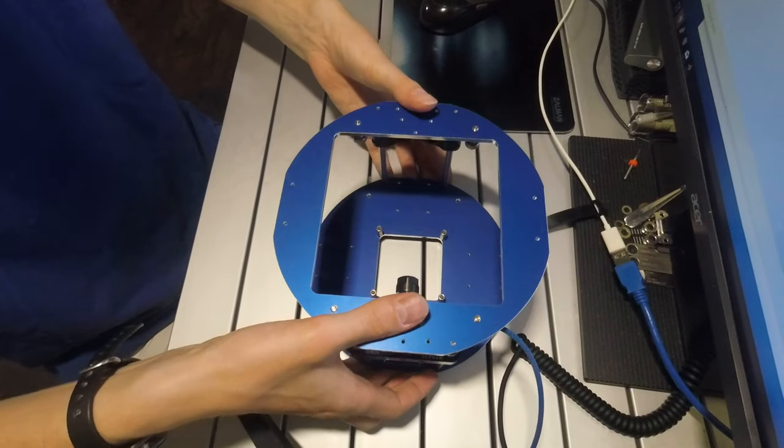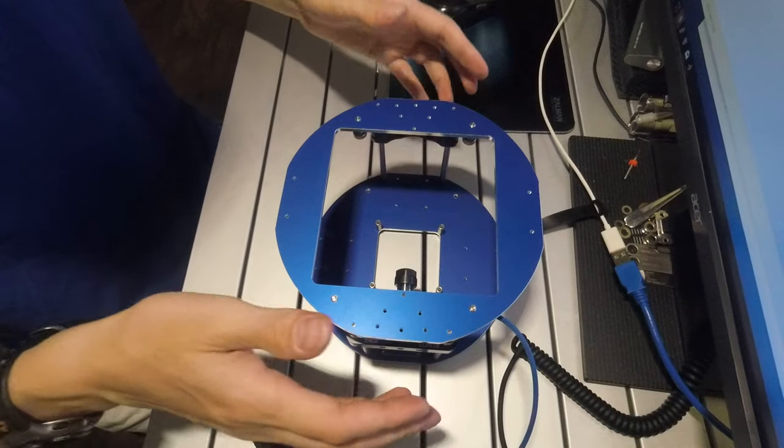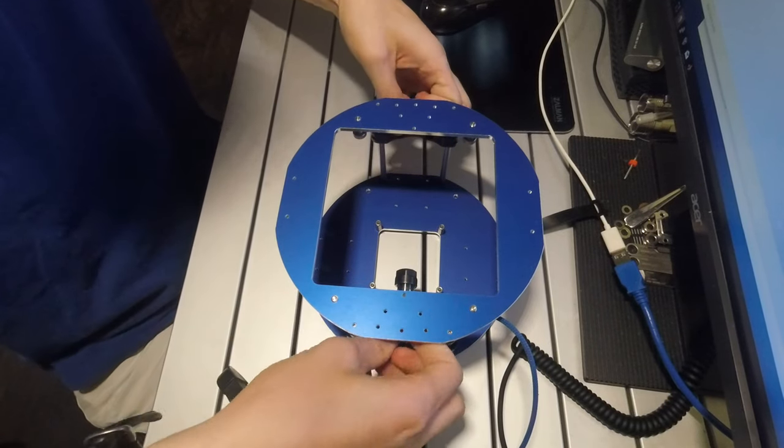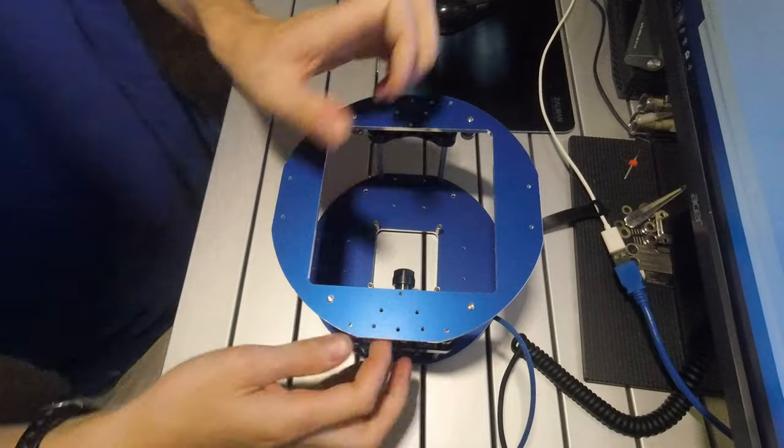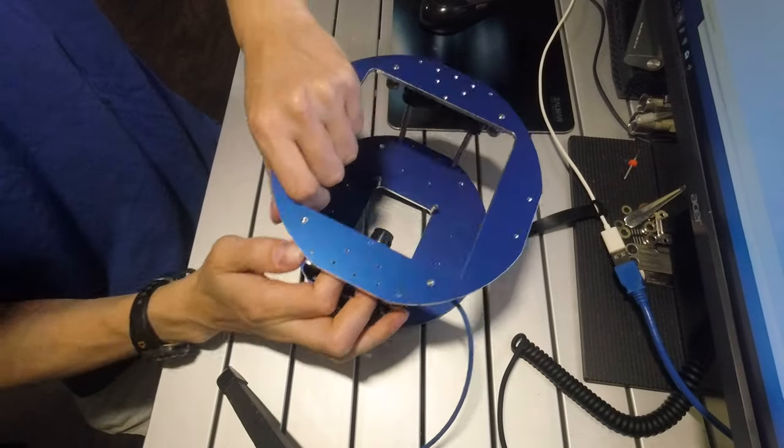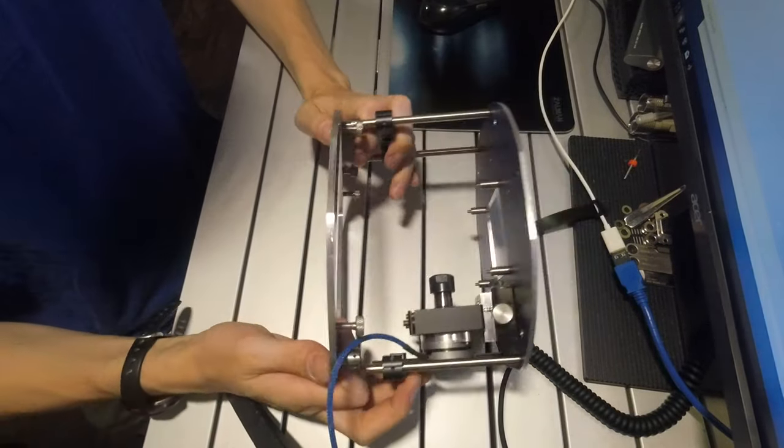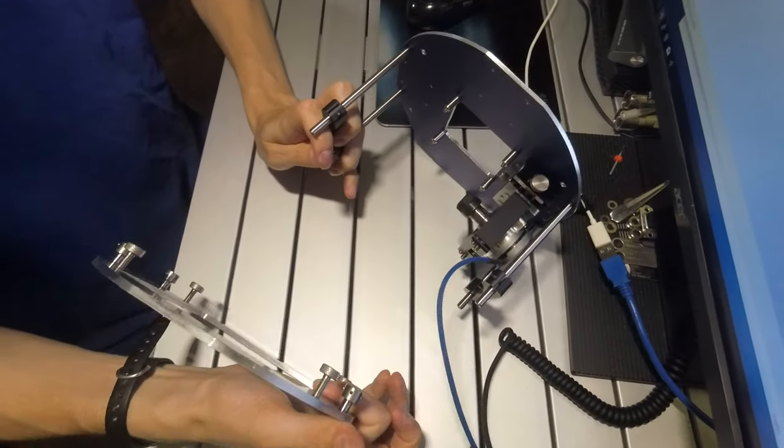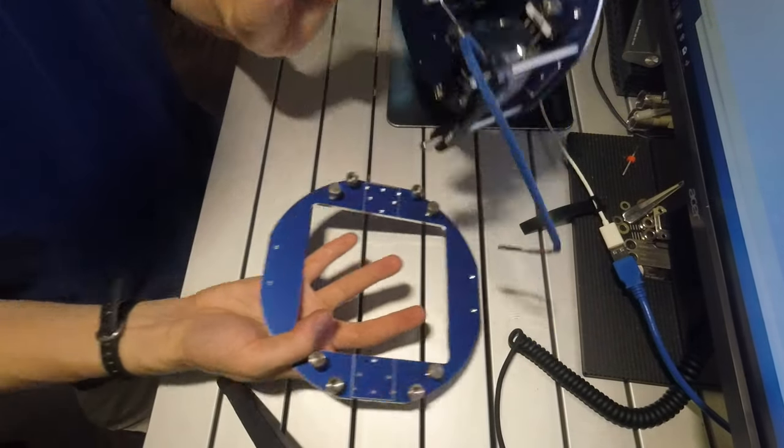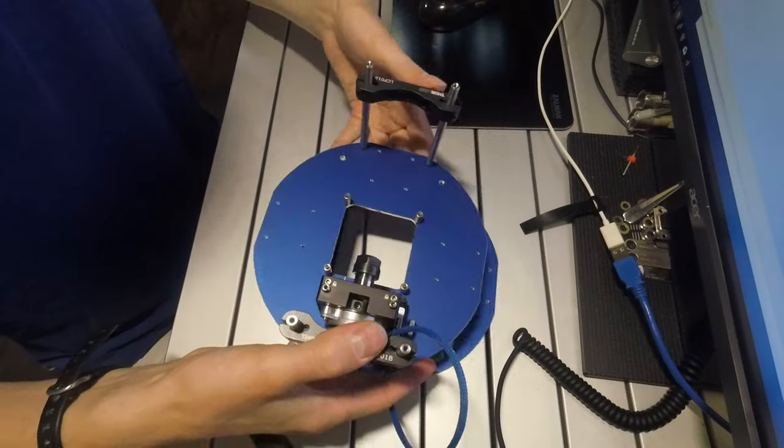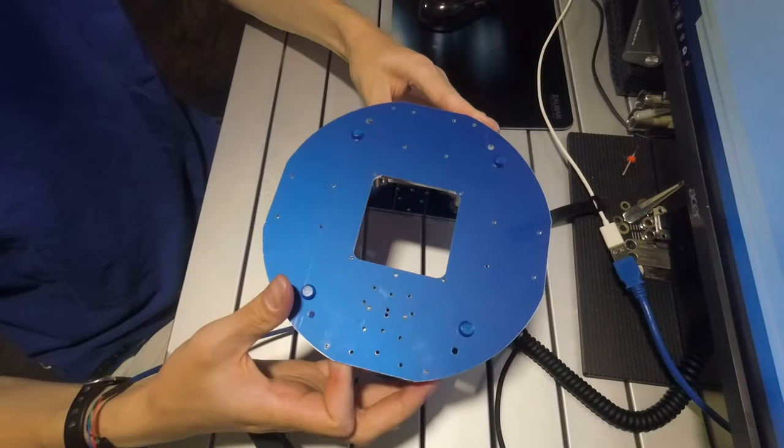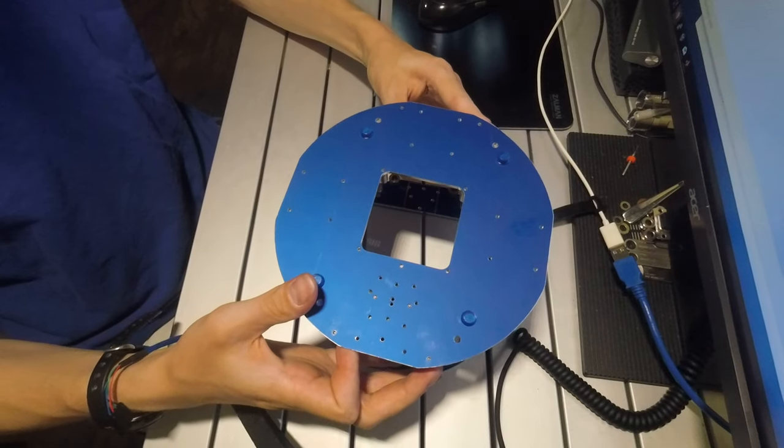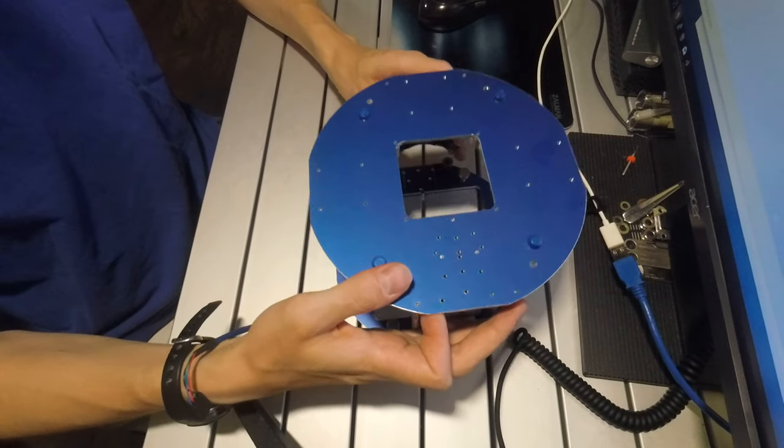Now because the imaging chamber has a little lip in it this is installed in two parts and they separate so the bottom and top of the stages come apart first the bottom is inserted in then the top section is inserted in and raised up a little and then it comes down and the ends of these rods insert in these sockets.